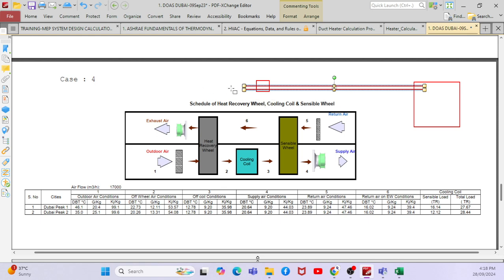The temperature outside is very cold, right? So when the fan runs, it will take air from outside and supply it at a low temperature. But this is a laboratory space, so you cannot have a low temperature. You have to maintain a normal temperature for the room condition. So to maintain this condition during the winter, you cannot provide air at low temperature. What you will do is add the duct heater. So you have to see in which condition you will add the duct heater, and that you have to find out.